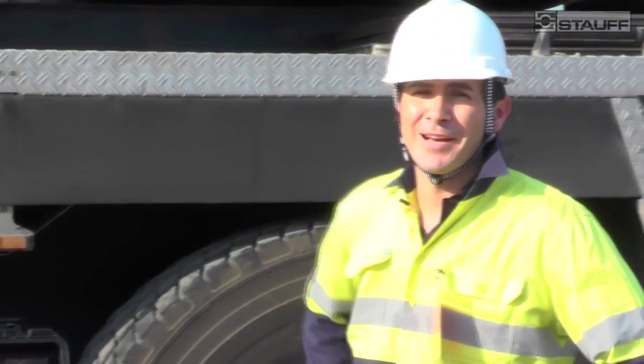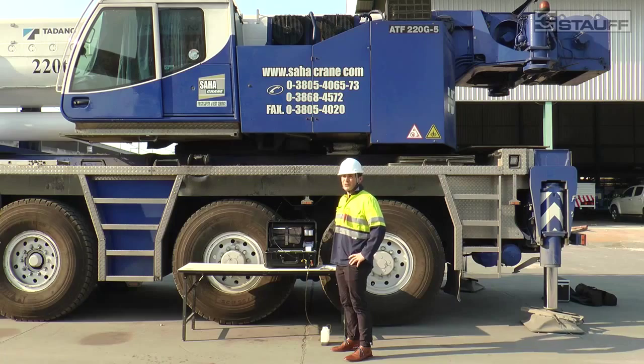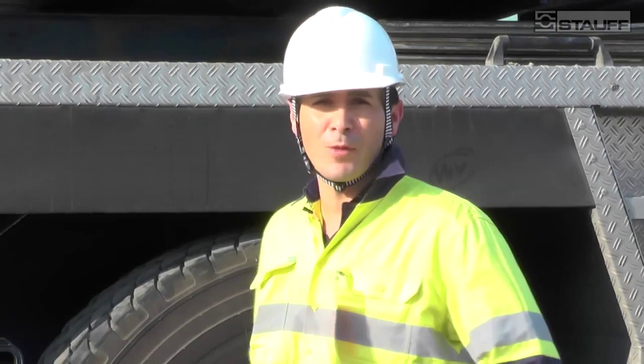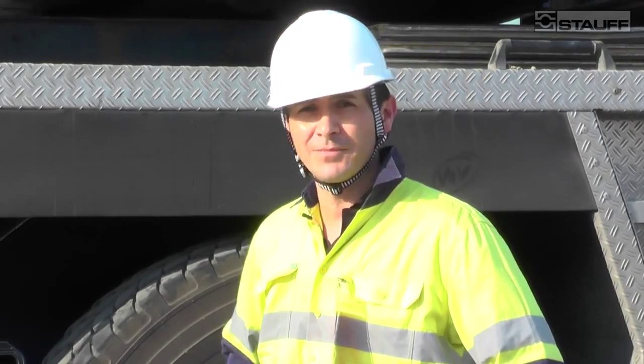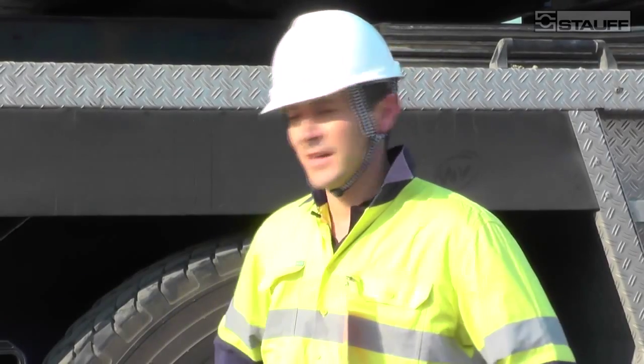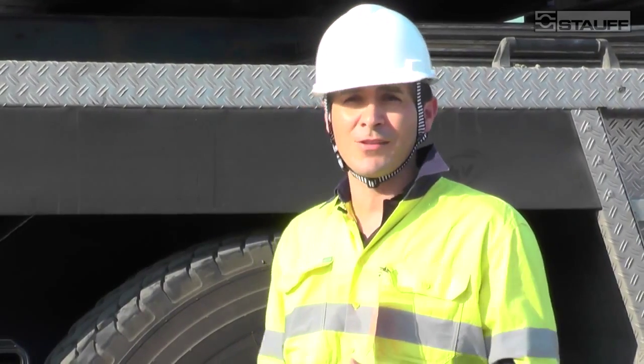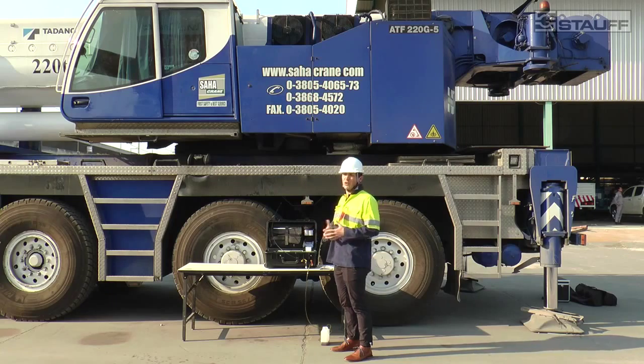So the STAUFF particle counter is actually very easy to use. You can use it in the workshop for previously sampled media. You can use it in the field. It very quickly provides you with the ISO cleanliness levels and the moisture content of the oil.